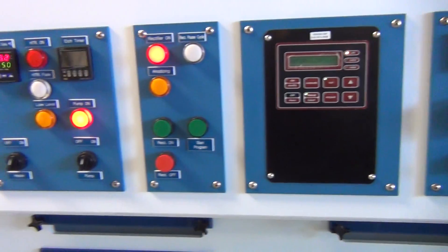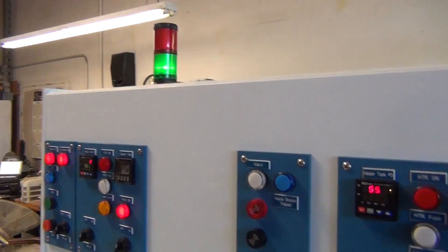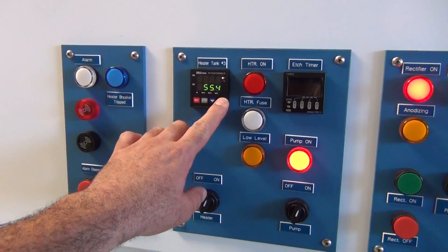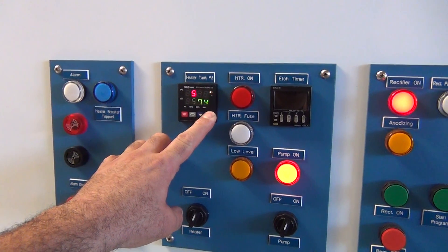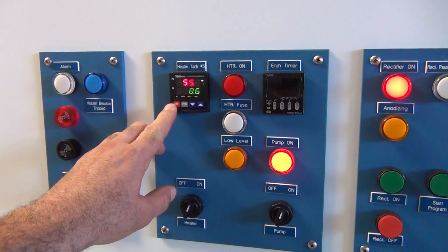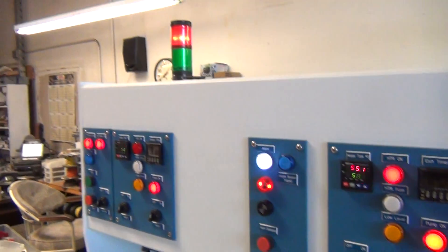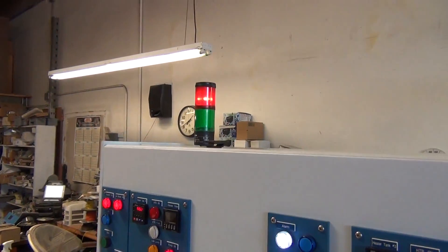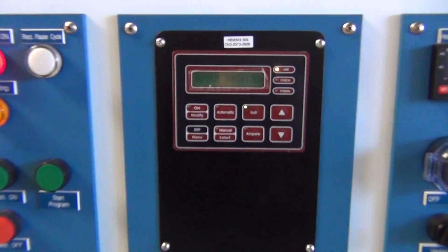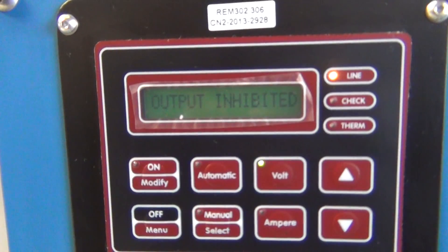We have the remote control tied to the red light. So if we are outside of temperature range, not only do we get an alarm saying there's a problem and get a red light, but the output on the power supply is affected.